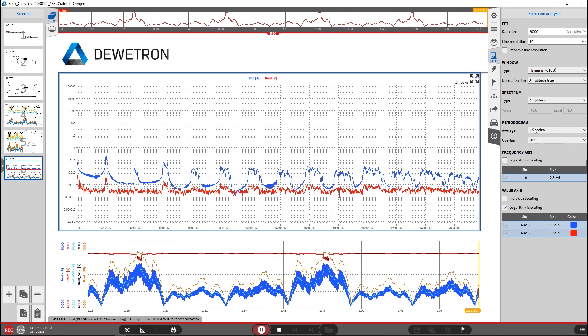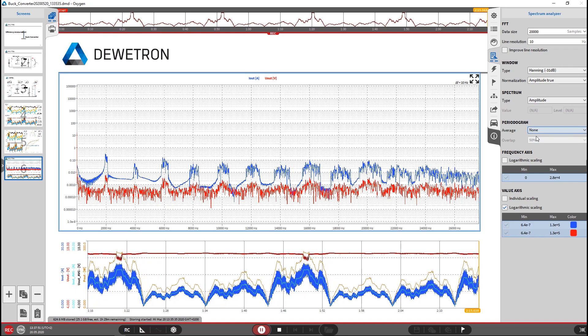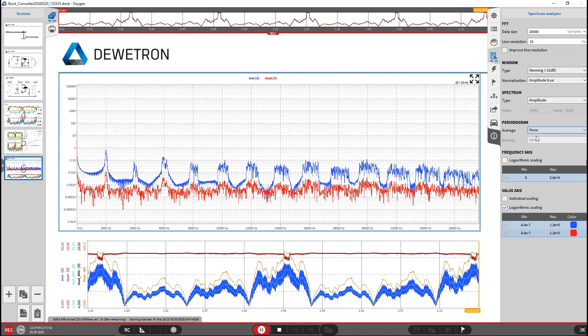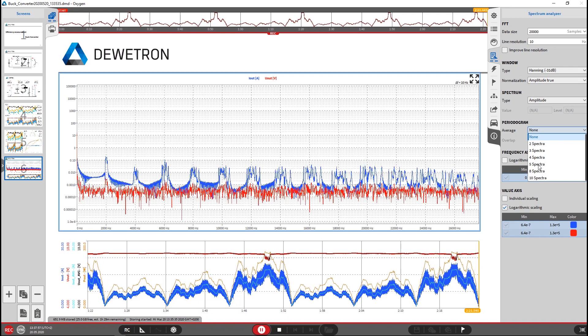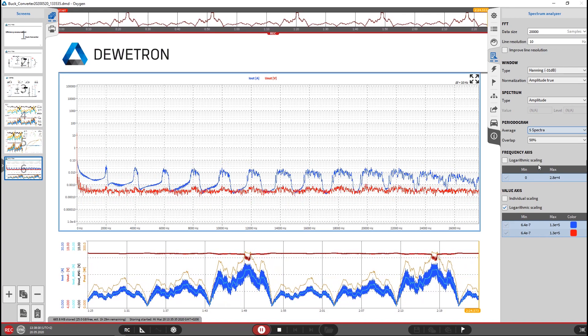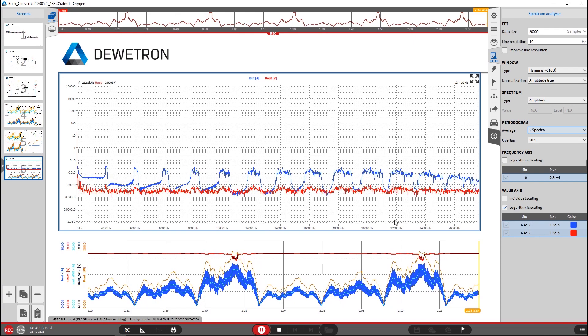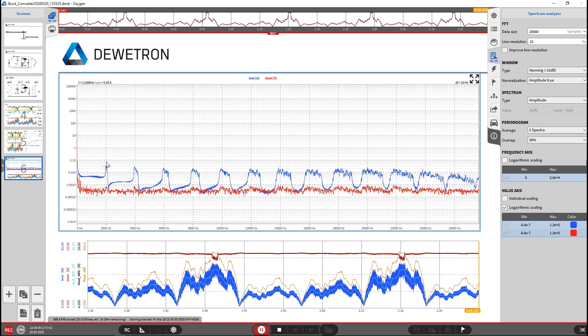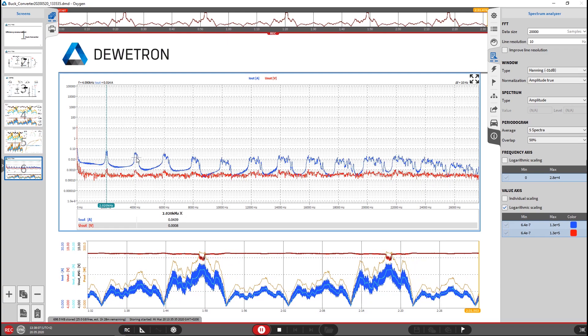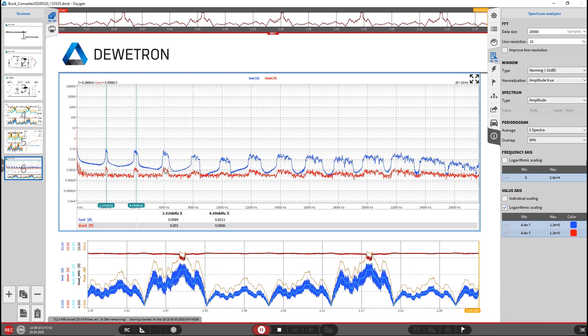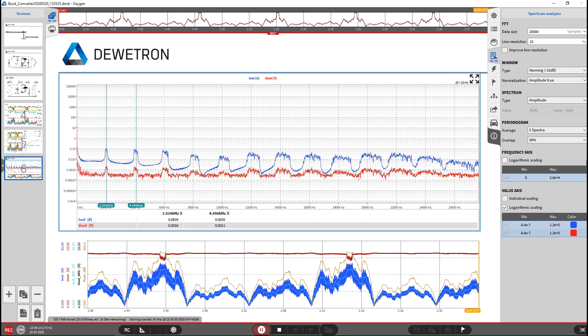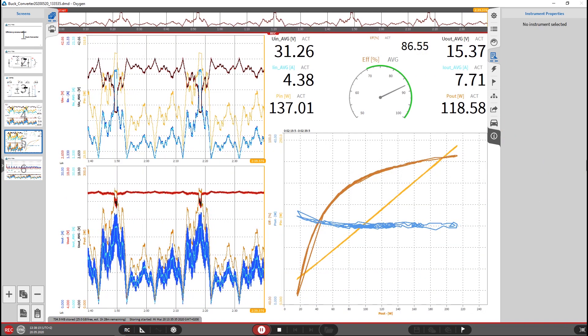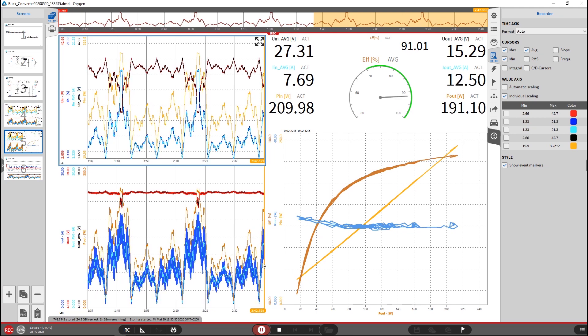This is a very clear picture because we have the possibility to average the spectra with an overlap function compared when I do not average it, we get much more noise and stochastic signals on it. And that's why it is recommended to average to get a really clear picture. And with the cursor values, we could here mark the harmonics and the superharmonics. So we could see this for current and voltage.